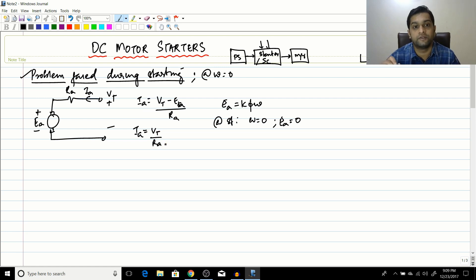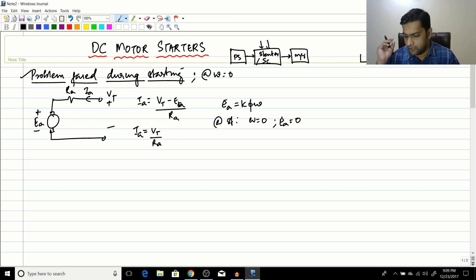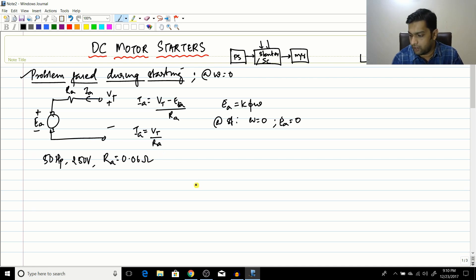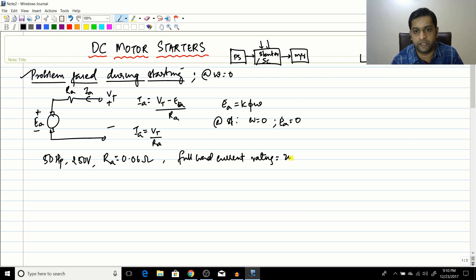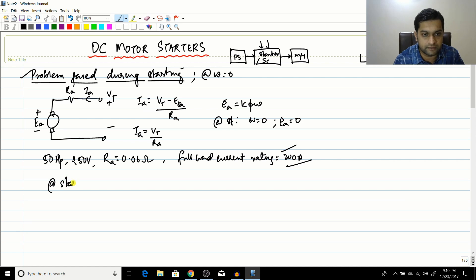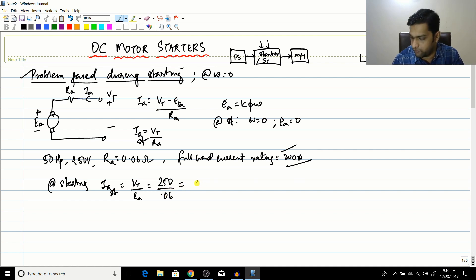The windings are not designed to handle such high current — insulation fails, windings heat up and burn. To illustrate the gravity of the situation: consider a 50 HP, 250 V motor with Ra = 0.06 ohms and a full-load current rating of 200 amperes. At starting, ia = Vt / Ra = 250 / 0.06, which equals approximately 4167 amperes.